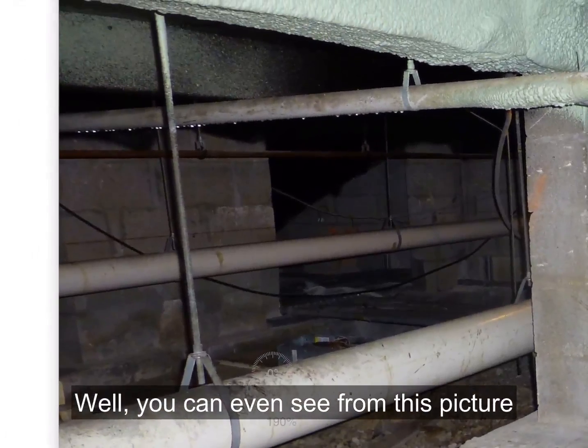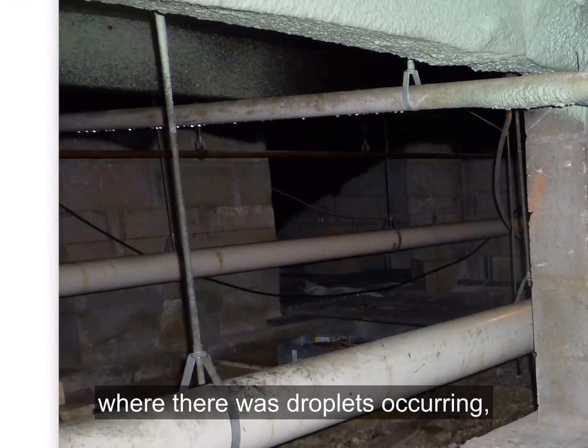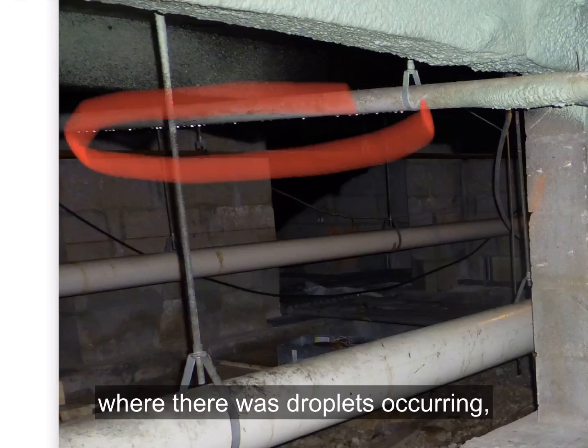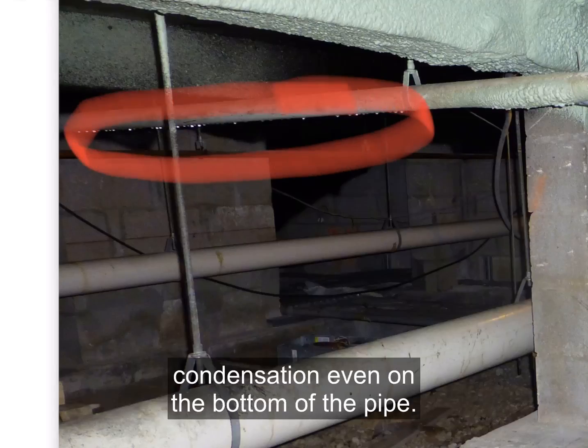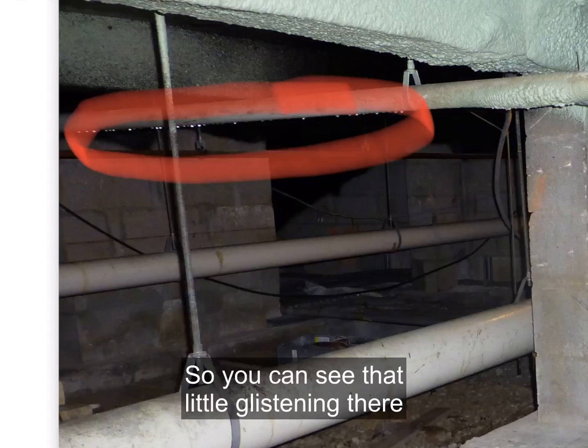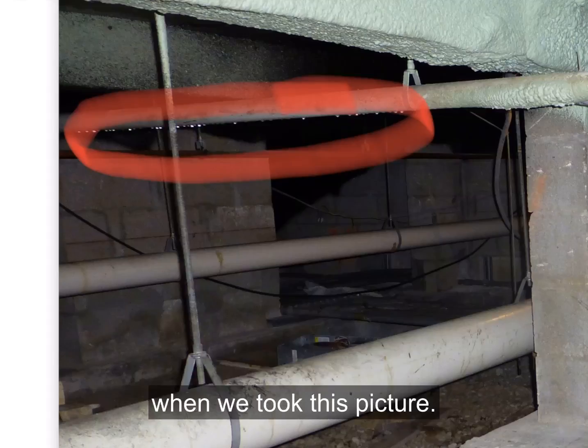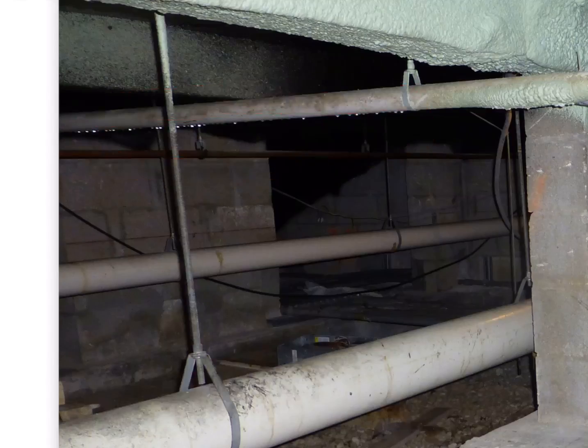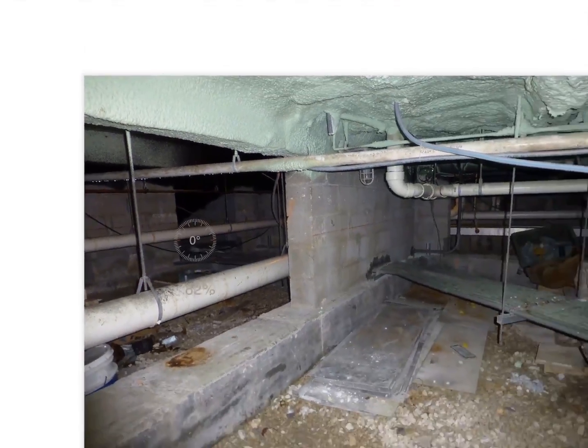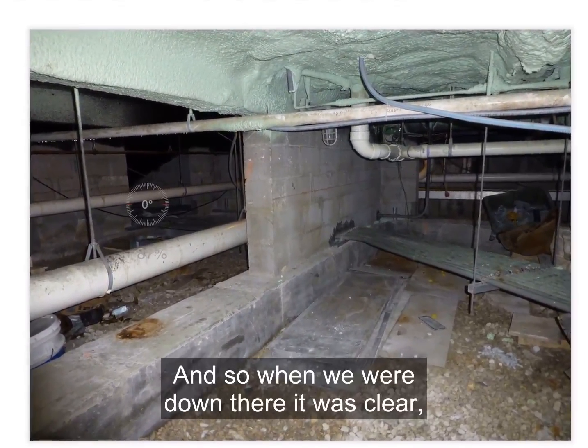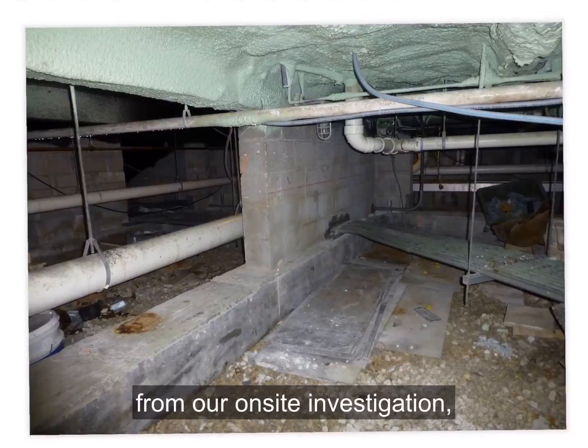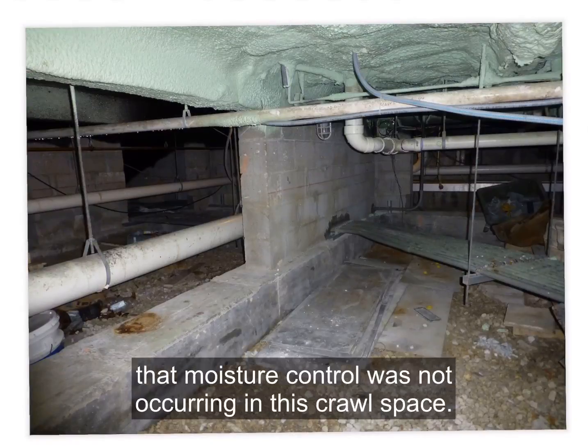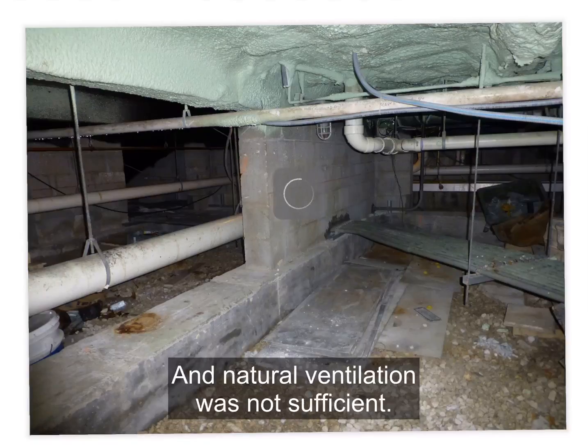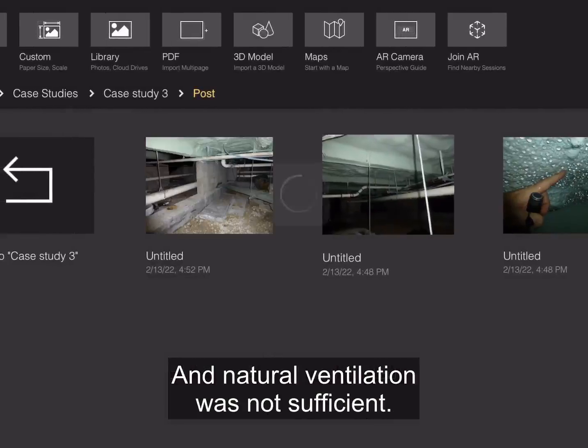Well, you can even see from this picture where there were droplets occurring, condensation, even on the bottom of the pipe. And so you can see a little glistening there when we took this picture. And so when we were down there, it was clear from our on-site investigation that moisture control was not occurring in this crawl space, and natural ventilation was not sufficient.